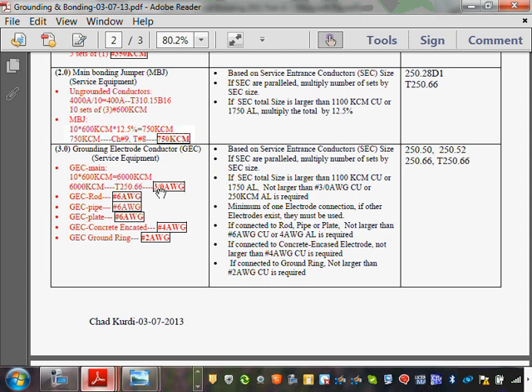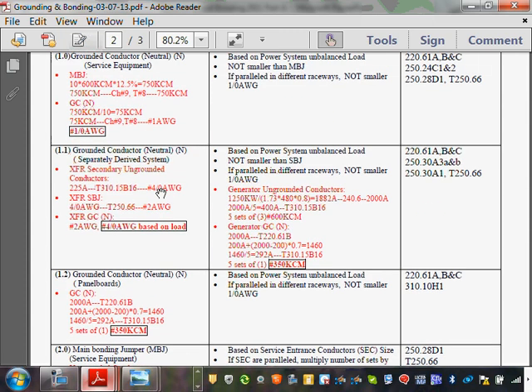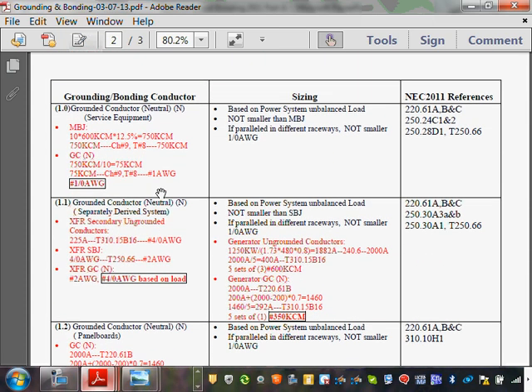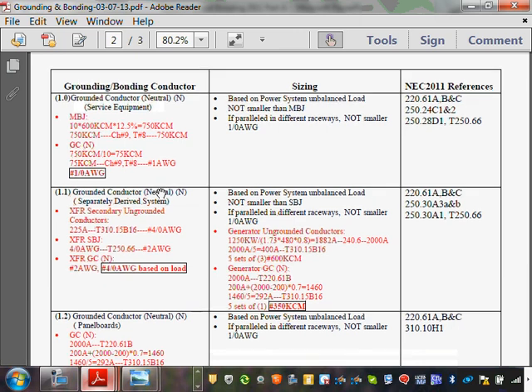If you remember how we sized at 10 way at the top, here's the size of my neutral, 750, but I divided it by 10 because I'm paralleling. So the size of your neutral will be 750 in one conduit. A system like this will be really hard though. Right? It will be hard to pull 10. To do this, you have to pull 10 600 kcmil conductors in one conduit. There is no conduit that I know of that can handle that. See what I mean? But that's how you size it.